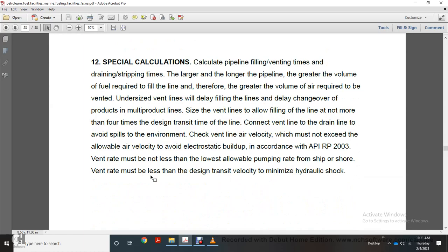Special calculations. Calculate pipeline filling, vent line, and draining and stripping times. The larger and longer the pipeline, the greater the volume of fuel required to fill the line, and therefore the greater the volume of air required to be vented. Undersized vent lines delay filling of the line, delay the changeover of product with the multi-line product. Size the vent lines to allow filling of the line in not more than 4 times the design transit time over the line.